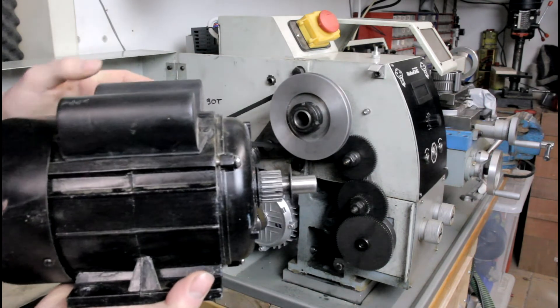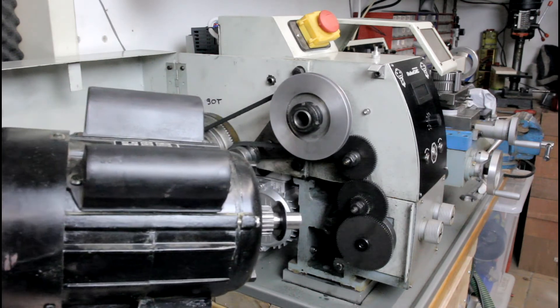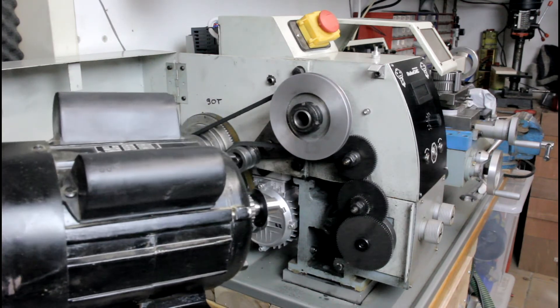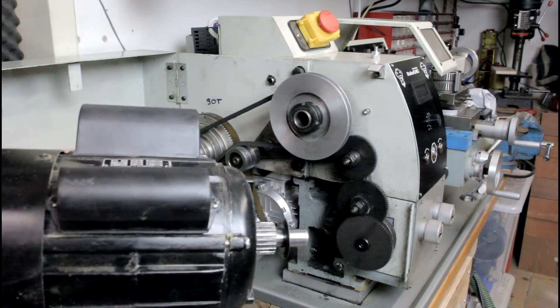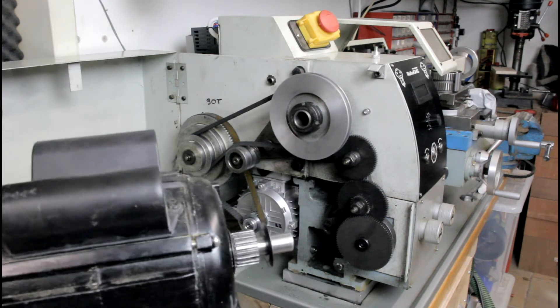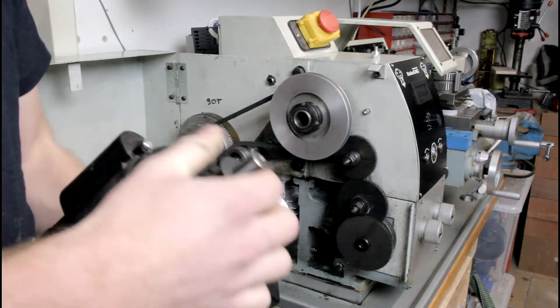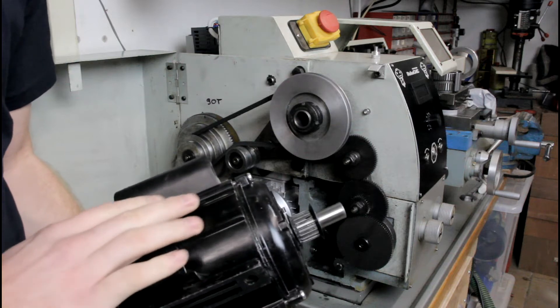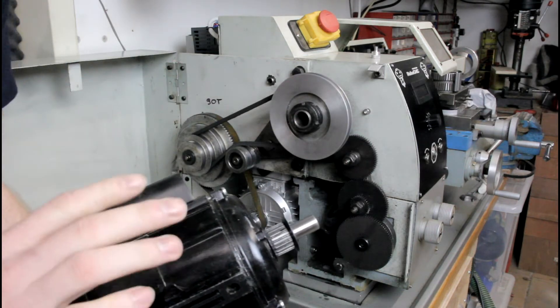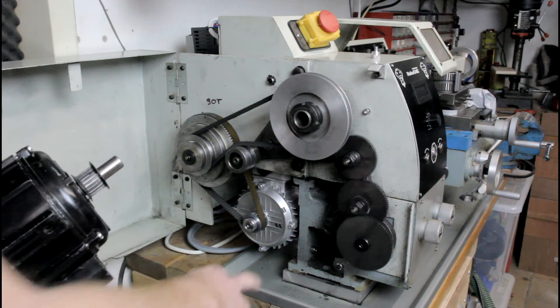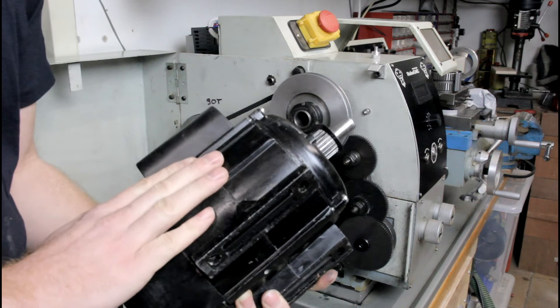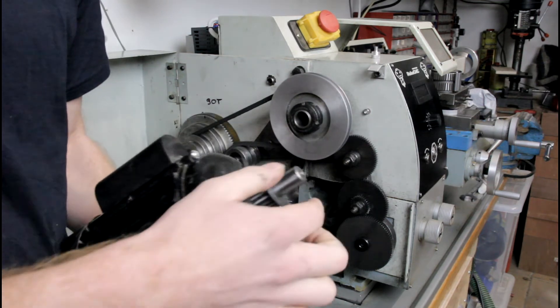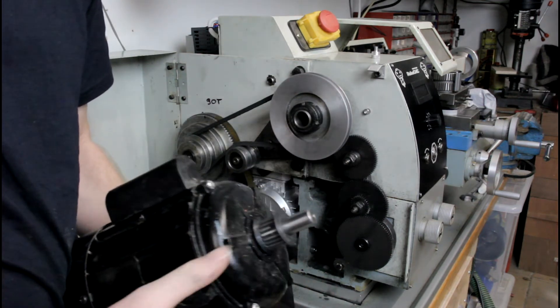The original motor was a single phase 230 volt motor, 550 watts, and they claim it to be about 3 Nm. This motor is not that standard. Most motors are standardized. This is a 71 size motor. This one is a 71 size motor except for the shaft. The shaft is wider and it is longer.